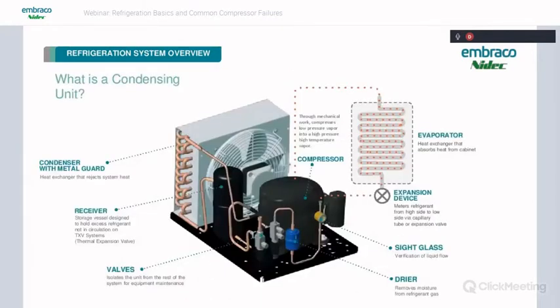So this slide shows a condensing unit. And what is a condensing unit? It's basically the complete high side of the refrigeration system, containing the condenser coil, the condenser fan, the compressor. In some systems, you'll see a receiver, which is just a refrigerant storage tank, usually used in systems with TXV valves or for larger commercial systems that have large charges, and you need a little bit extra space to store that refrigerant in the off cycle.